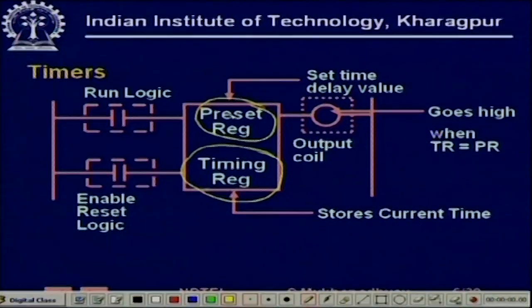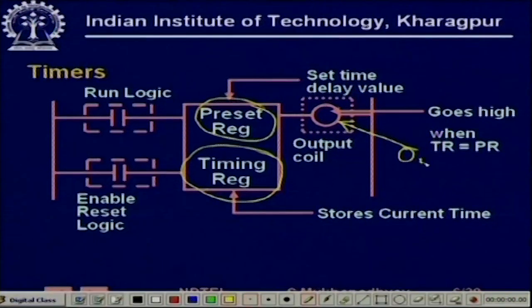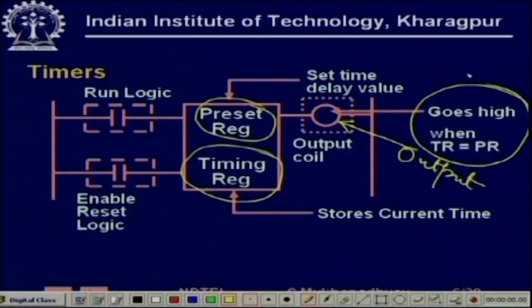The timer does not require any external clock — though counters, as we shall see, work on an external clock. The timing pulses come from the internal clock, so the timing register keeps increasing. There is a continuous comparison between the timing register and the preset register. After some time, the timing register value will exceed the preset register value, at which point the timer stops timing further — the timing register stops incrementing — and the output is asserted. So the output is asserted when the timing register equals the preset register.